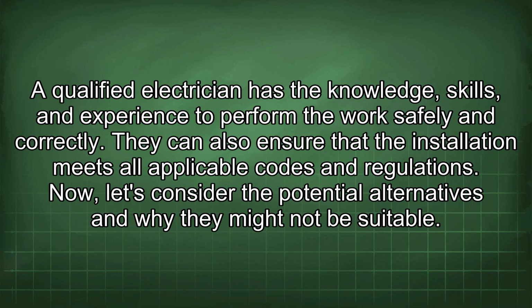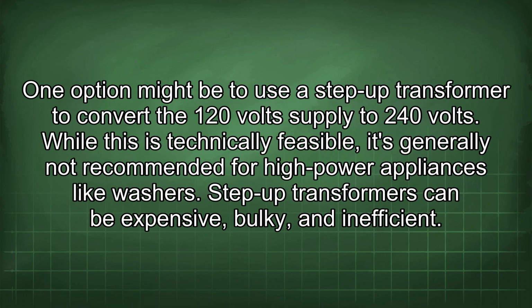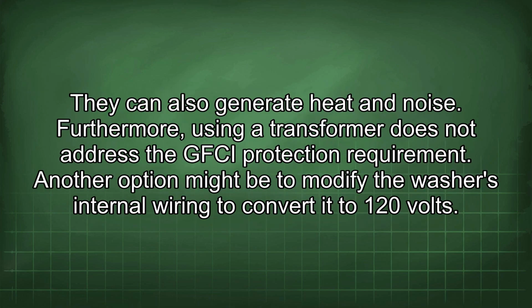Now, let's consider the potential alternatives and why they might not be suitable. One option might be to use a step-up transformer to convert the 120-volt supply to 240 volts. While this is technically feasible, it's generally not recommended for high-power appliances like washers. Step-up transformers can be expensive, bulky, and inefficient. They can also generate heat and noise. Furthermore, using a transformer does not address the GFCI protection requirement.